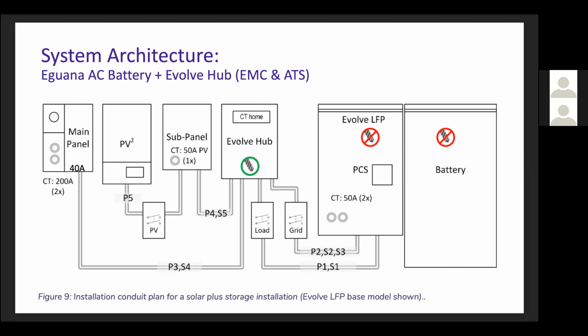The good thing about this Evolve Hub is that, as per the 2020 NEC 705.13, I believe, PCS controls, the Evolve Hub monitors in real time what the PV production is, and based on that level of PV generation, it controls or limits the battery's discharge to be whatever the PV is, so that the total never exceeds that 40 amps. So you could have this 5 kW grid tied battery inverter plus a 7600 watt SolarEdge inverter, for example, all connected through a single 40 amp breaker, which normally would completely exceed that rating.